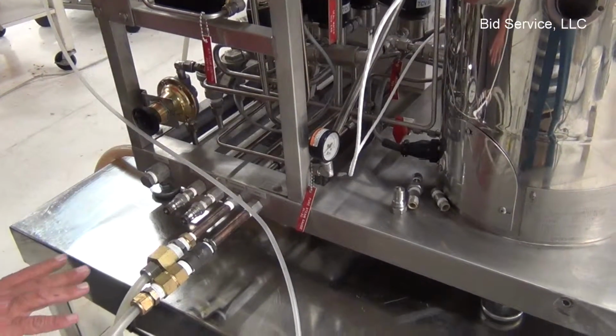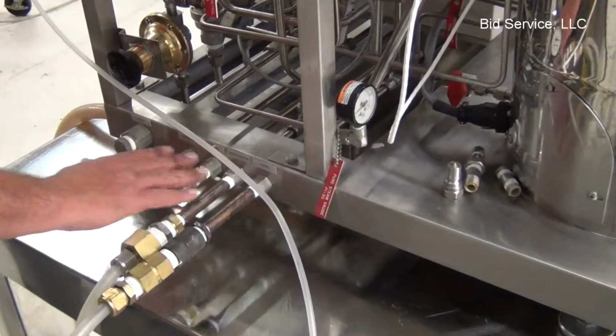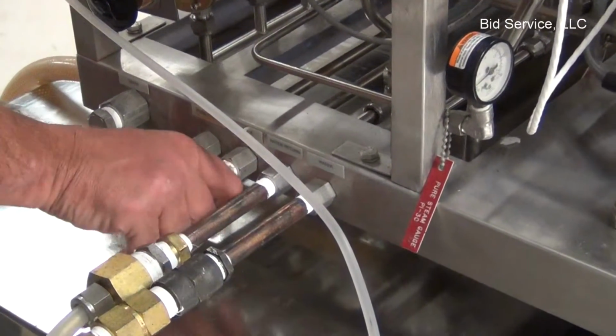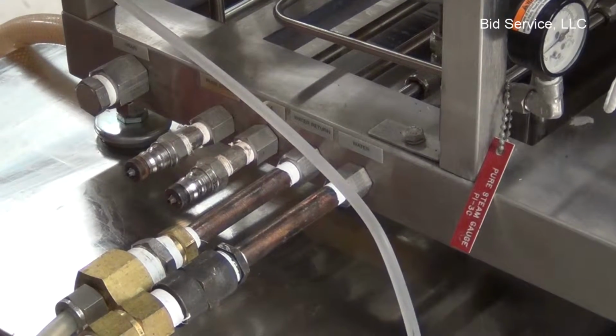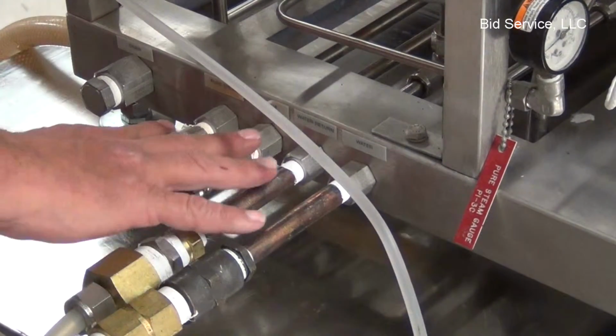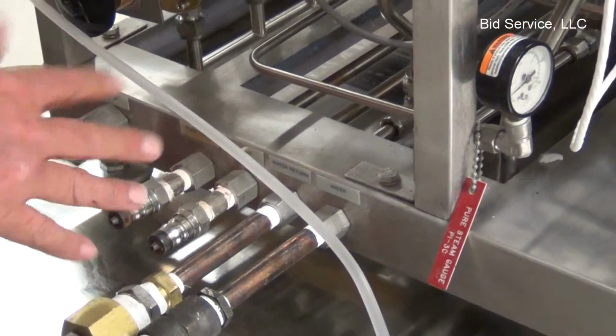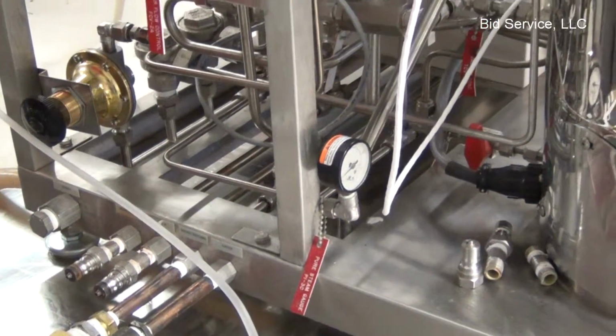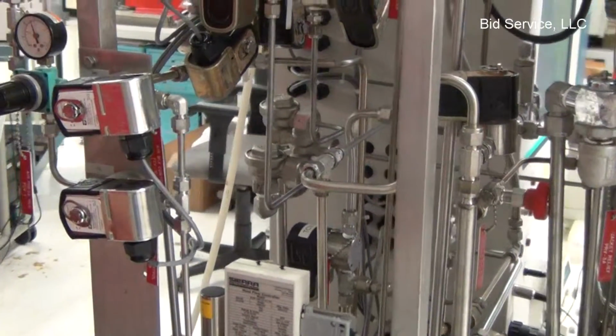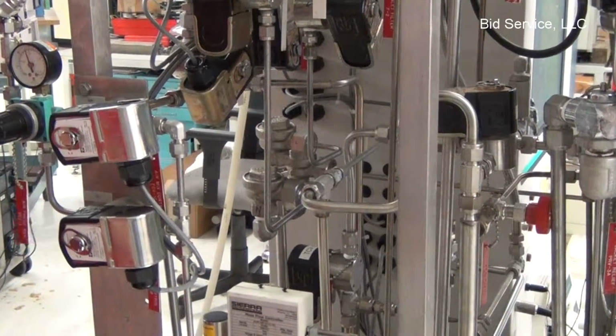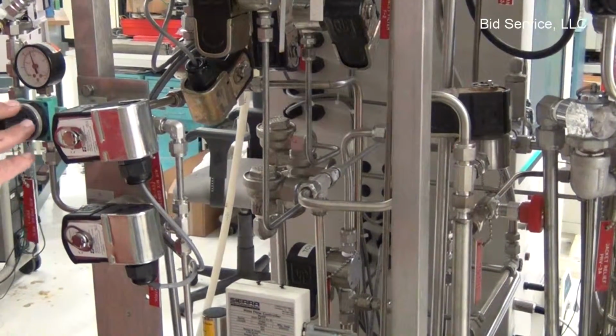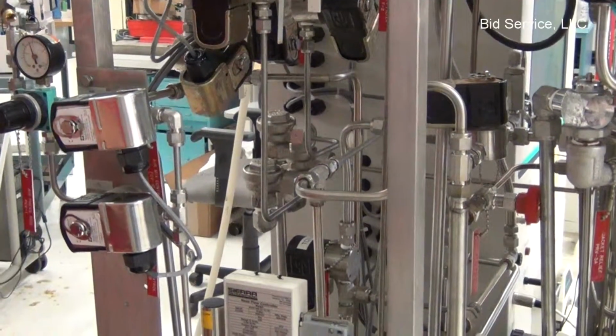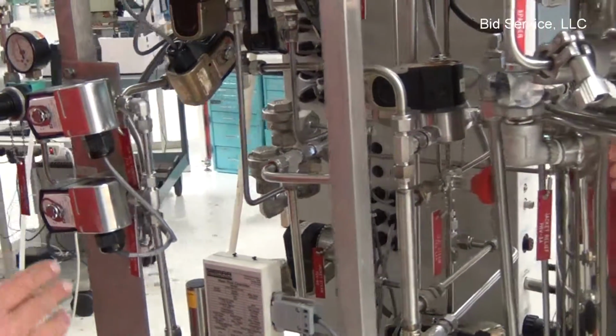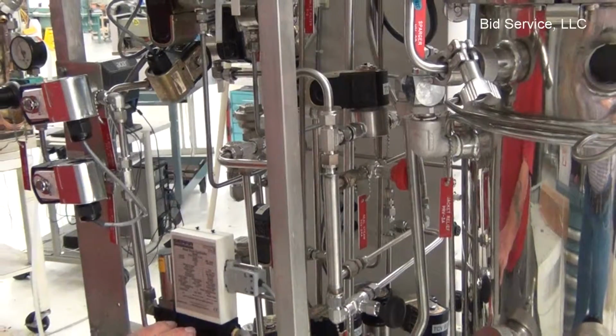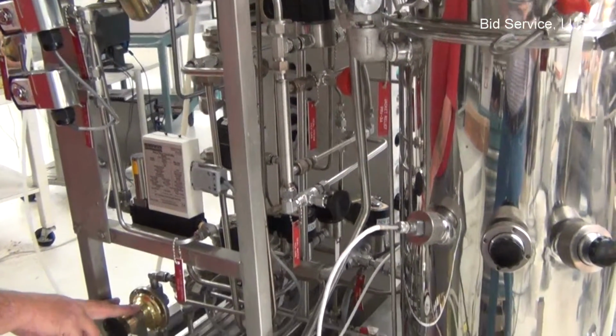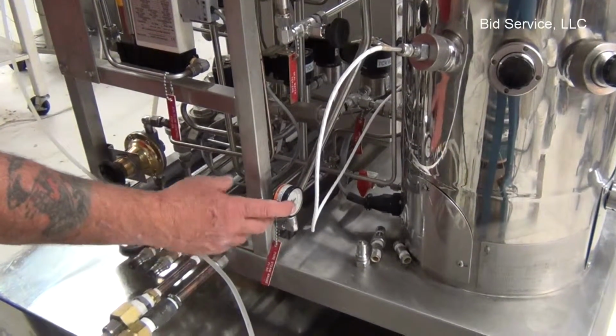Okay, we're on the left side of the instrument. Just wanted to point out where things are connected. This is your water in and water out. Your steam for sterilization would be here, and then the drain. Now this drain is actually connected on the other side. All of these lines go underneath the instrument, and these connections can be put on either side. Up here, this is your air in and oxygen if you wanted to do that. And right now I've got it set to about 15 pounds. There's quick connects that came with the system, which I'll include, but I took that off to enable my connections. The mass flow controller, which determines your flow rate and the pressure, and your back pressure gauge is here. Back pressure gauge you can read right on the front here.